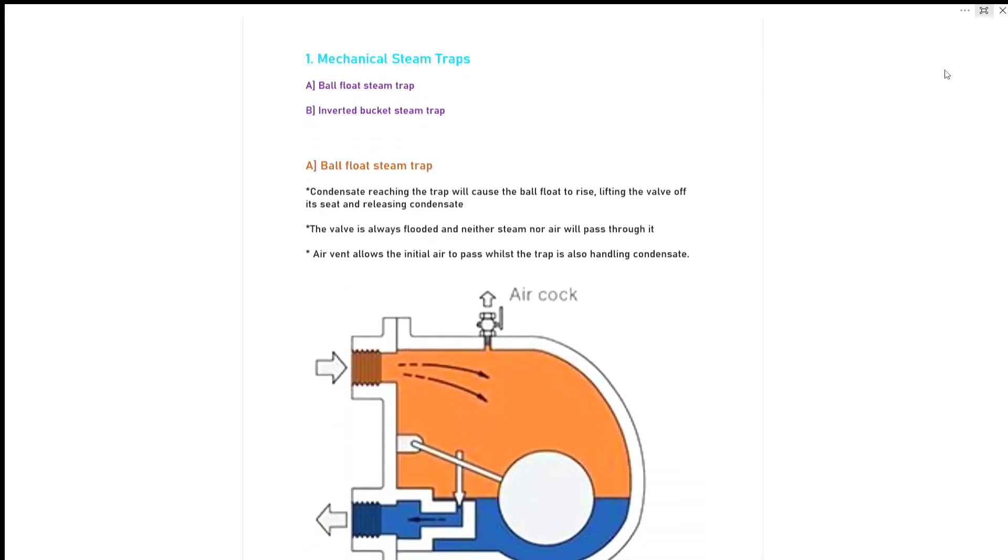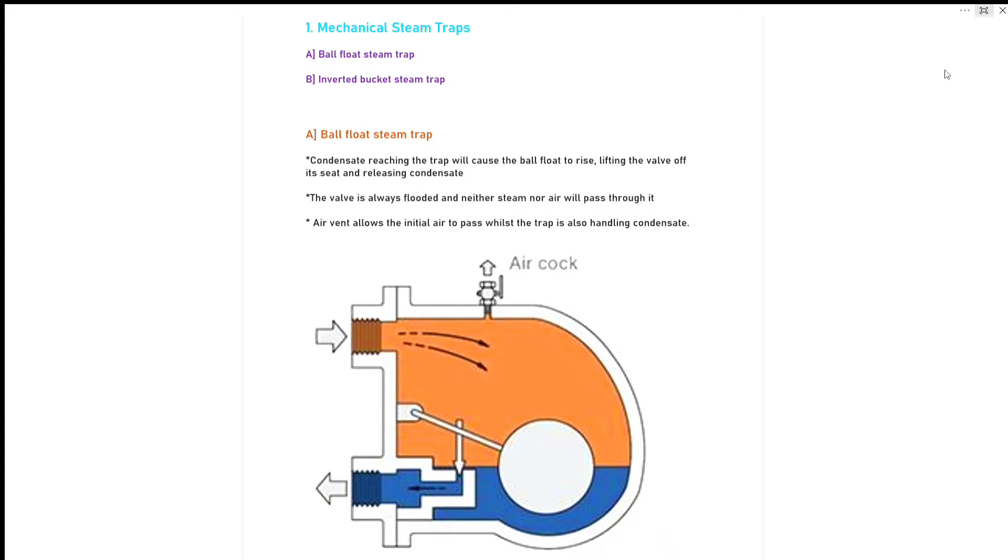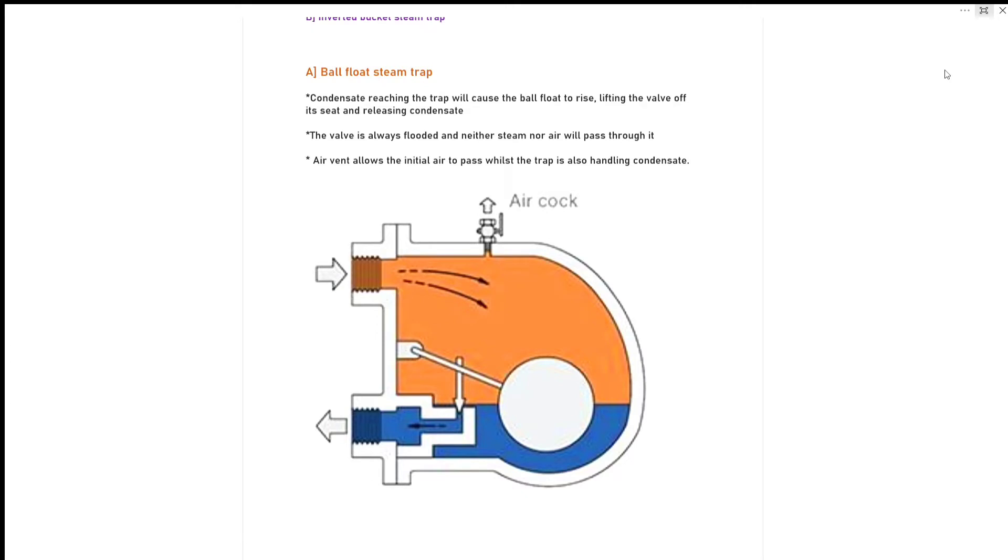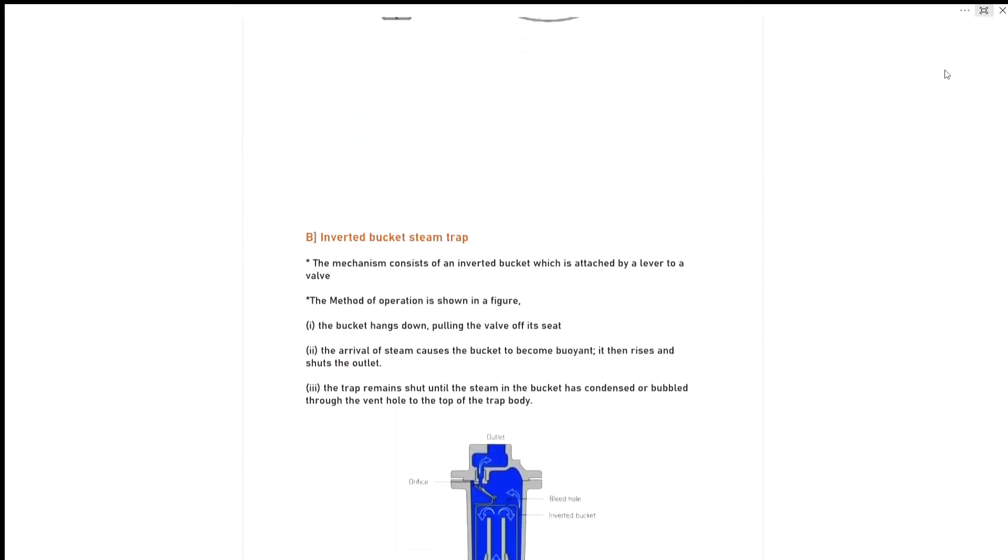Mechanical steam trap has two types: one is ball float steam trap and second one is inverted bucket steam trap. So first we will discuss ball float steam trap. Condensate reaching the trap will cause the ball float to rise, lifting the valve off its seat and releasing the condensate. The valve is always flooded and neither steam nor air will pass through it. Air vent allows the initial air to pass while the trap is also handling condensate. So you can see this diagram here of ball float steam trap.